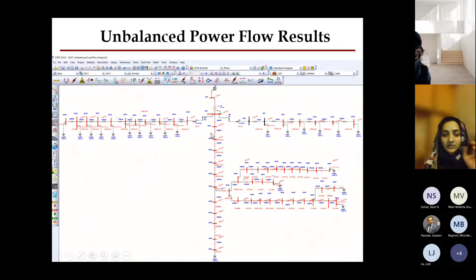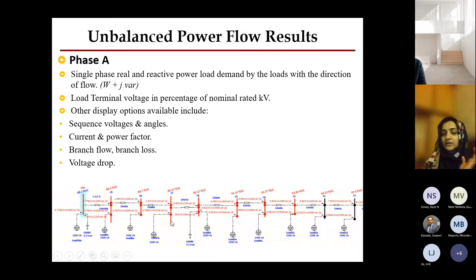These are again the phase A part results, but the main issue we got is some under voltage at the end of the load. We have multiple options to address this: using capacitor banks here, changing the transformer tappings, or adding PV and batteries, just to see how we can improve it.